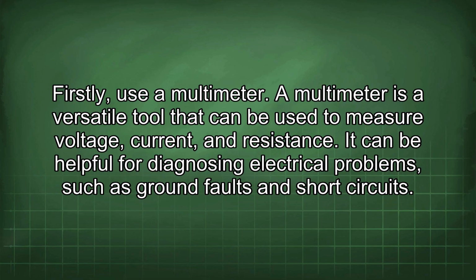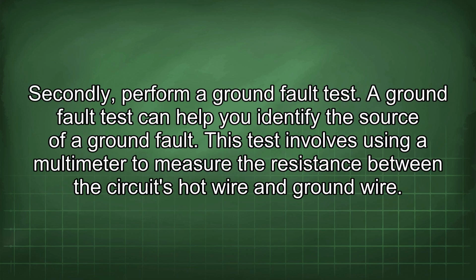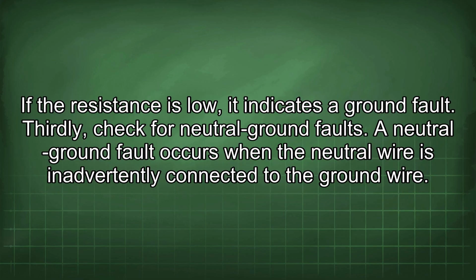Firstly, use a multimeter. A multimeter is a versatile tool that can be used to measure voltage, current, and resistance. It can be helpful for diagnosing electrical problems, such as ground faults and short circuits. Secondly, perform a ground fault test. A ground fault test can help you identify the source of a ground fault. This test involves using a multimeter to measure the resistance between the circuit's hot wire and ground wire. If the resistance is low, it indicates a ground fault.